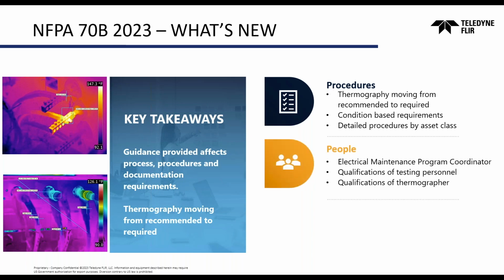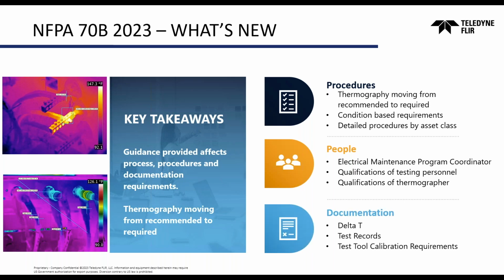On the people side: understanding the role of the electrical maintenance program coordinator, as well as qualifications of both the testing personnel and the thermographer themselves. And lastly, documentation: understanding delta T, temperature differences, test records themselves, as well as calibration requirements that are all an important part of this standard.